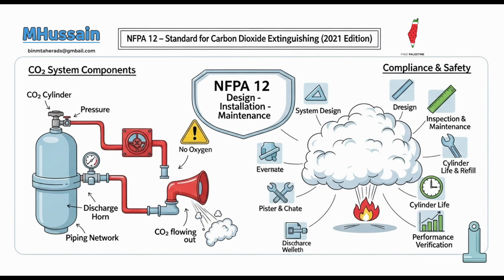Test hoses every 5 years. This involves a hydrostatic test at high pressures, 2,500 psi, 17,239 kPa for high-pressure systems, and 900 psi, 6,205 kPa for low-pressure systems, where the hose is removed, filled with water, pressurized for a minute, and observed for distortion or leakage. Pressure test with water. Electrical continuity is also checked for hand lines. Hoses that pass are marked with the test date, while those that fail are destroyed and replaced. Mark good hoses, destroy bad ones.